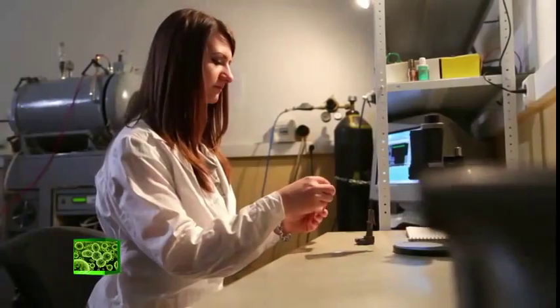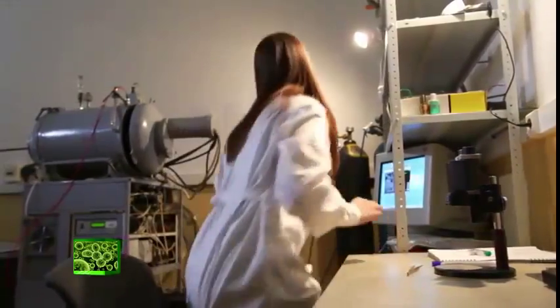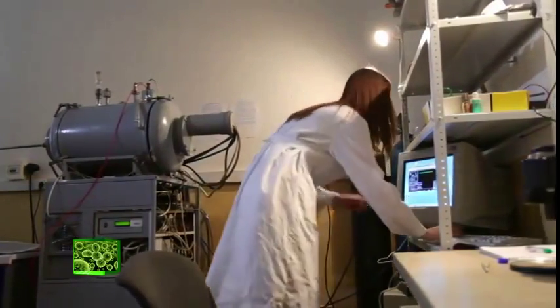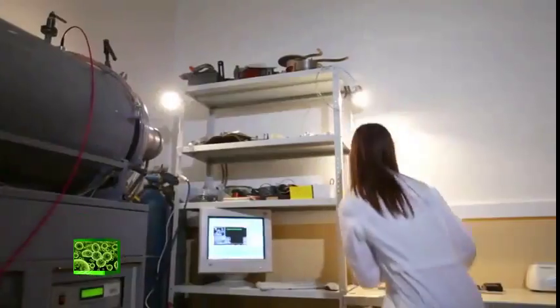As well as modifying bone implants, researchers have started developing ultra-thin coatings for coronary stents. Any malfunction of the cardiovascular system could be lethal, which is why searching for new ways to prolong the life of patients is of utmost importance. Stents are small mesh tubes expanded to keep weak or narrow arteries open, but delicate arteries can be damaged during the implant operation. To avoid complications, the stents are coated in titanium nitride oxide, or TNO. This super-smooth coating helps avoid arterial damage, promotes healing, and significantly reduces the risk of blood clots or the artery collapsing again. The coating also remains intact as the mesh tube is expanded within the artery.